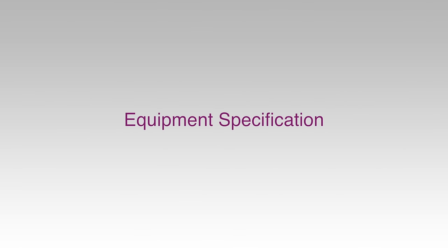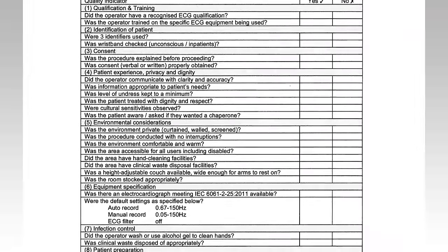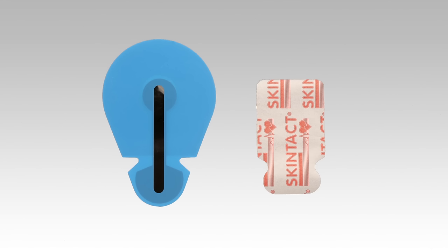The electrocardiograph must meet or exceed IEC standards. To avoid distortion of the ST segment, the low-frequency cut-off should be no higher than 0.67 Hz in auto mode or 0.05 Hz in manual mode. To prevent the loss of high-frequency information, the high-frequency cut-off should be no lower than 150 Hz in adults and 250 Hz in children. The disposable TAB electrodes should all be of the same make or type and meet or exceed the requirements of current guidelines.